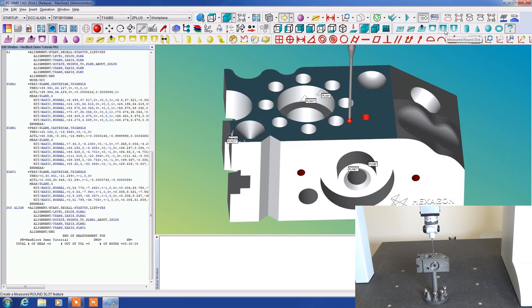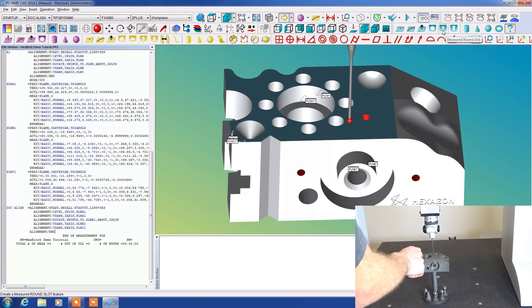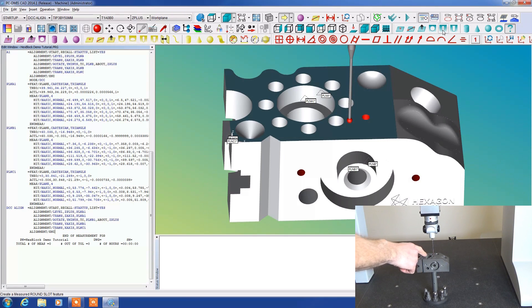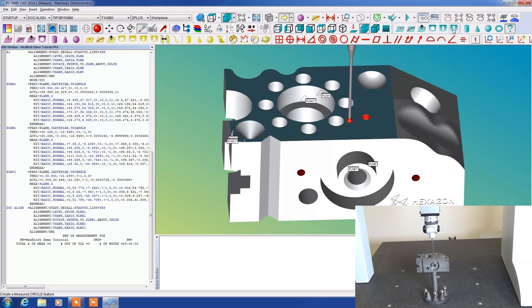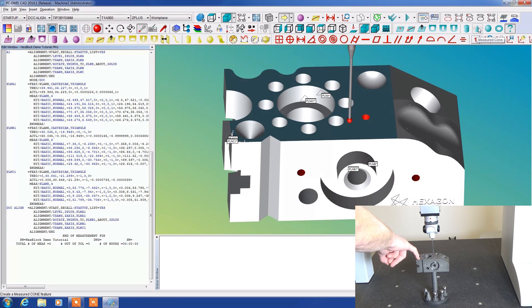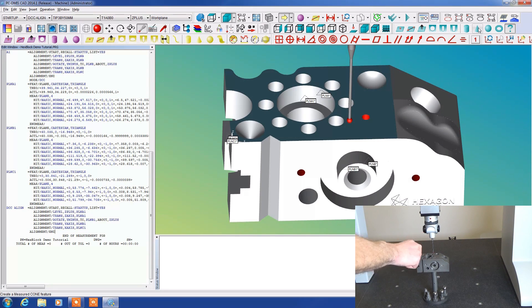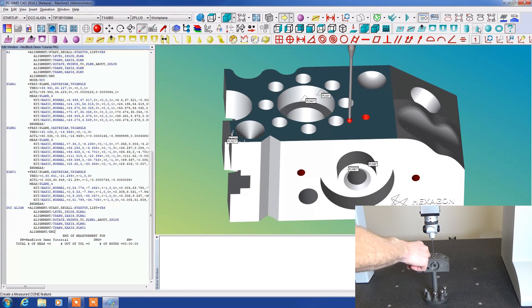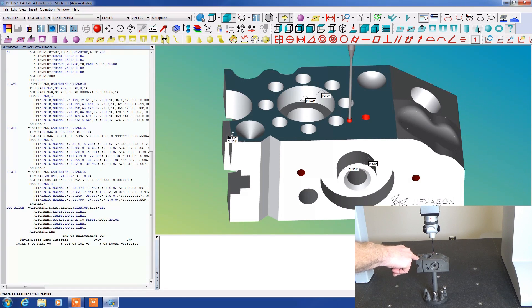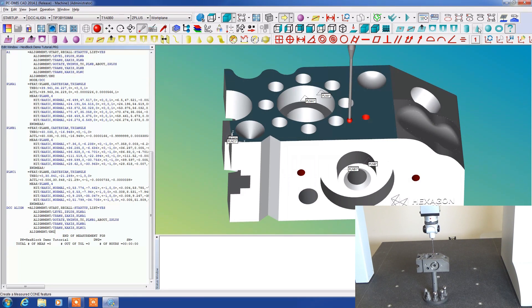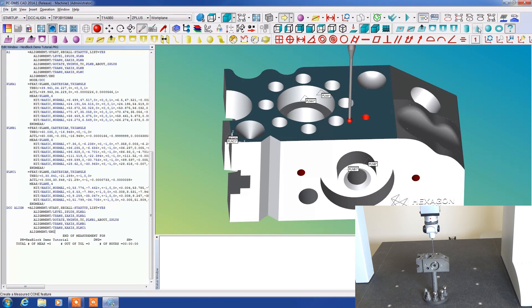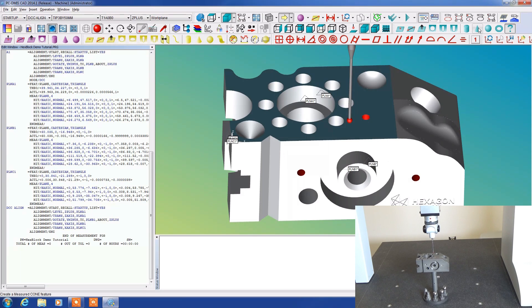A round slot, we don't really have a good example of it here, but if we did have a round slot you would want to take several measurements around that slot in the same plane. Same thing with the square slot or a measured cone. We have an inverted cone on this part but it works a lot like cylinder. You want to take three around the top at the same plane and then a few others at different levels throughout. It is a tough one for using guess mode. I found from experience that trying to measure a cone with guess mode will often come back with something different so just be aware of that.